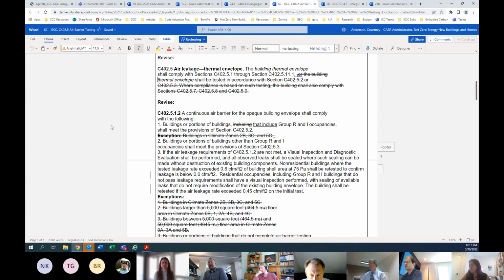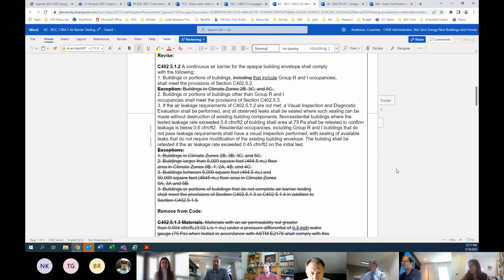It would include Group R and I occupancies. Some of this is existing, but for the buildings that are tested, they're tested to meet the air leakage requirements, and if they're not met, a visual inspection and diagnostic testing shall be performed, and all leaks shall be sealed where such leaks can be made without destruction of existing building components. Then it would be retested to verify that the leakage rate was no greater than 0.6 CFM per square foot of building shell area at 75 pascals.